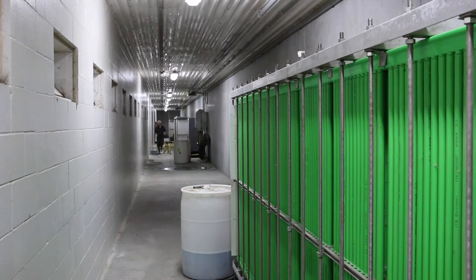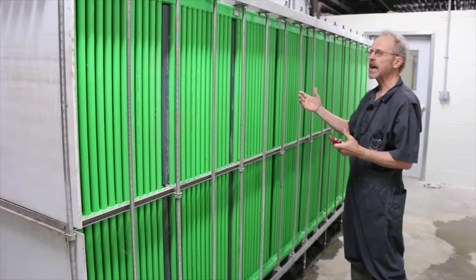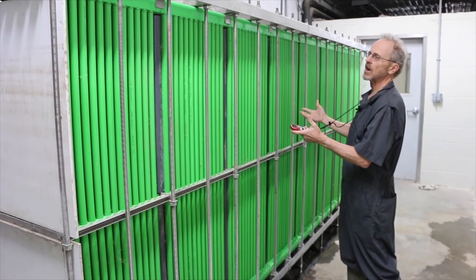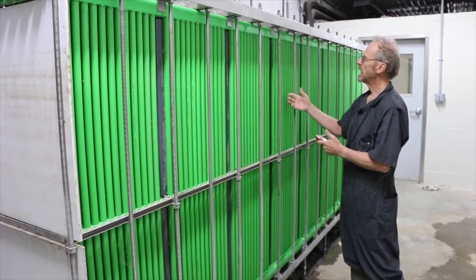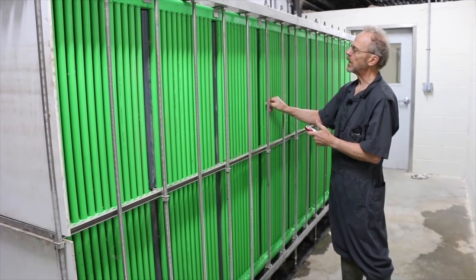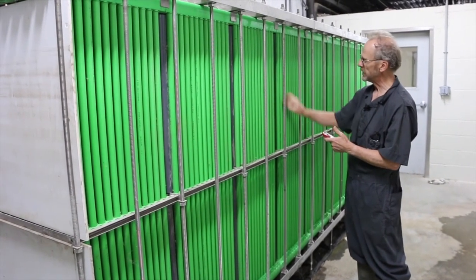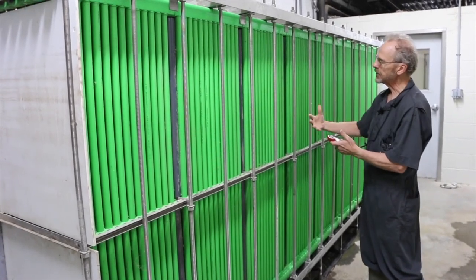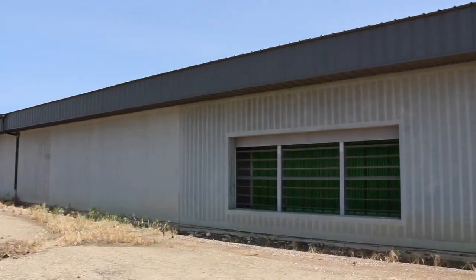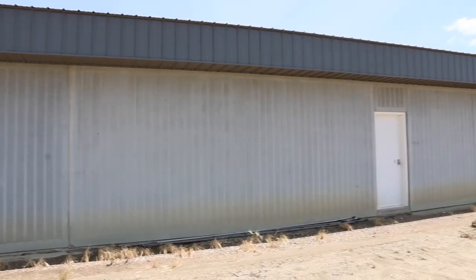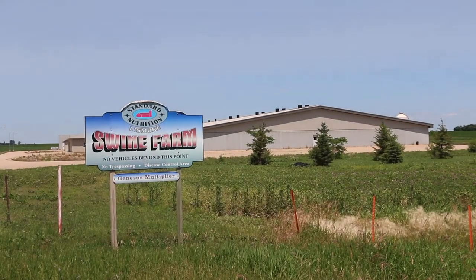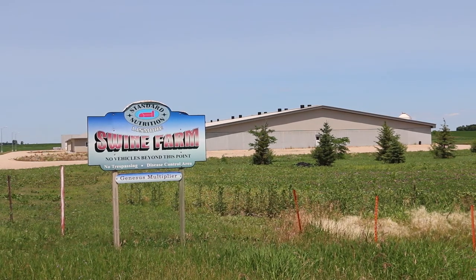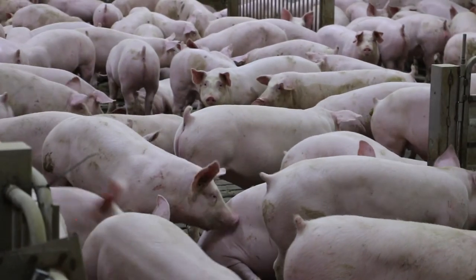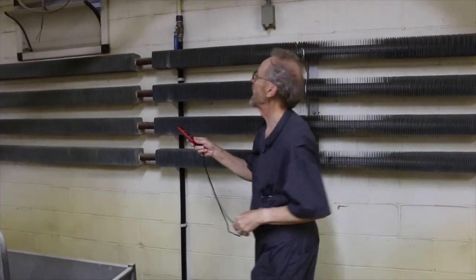The cooled fluid is pumped into a heat exchanger coil that is positioned in front of the inlet airstream. All the outside air is drawn in through this large, essentially radiator heat exchanger, and the cooled fluid that goes down into the wells is inside these pipes. And as the air comes through, it cools off. The number of loops or wells in the system is based on the amount of cooling needed. At the sow farm in western Minnesota, the geothermal system uses one well for every three pigs on the gestation farrowing site. About 60 degrees is the temperature of the air that's coming in.